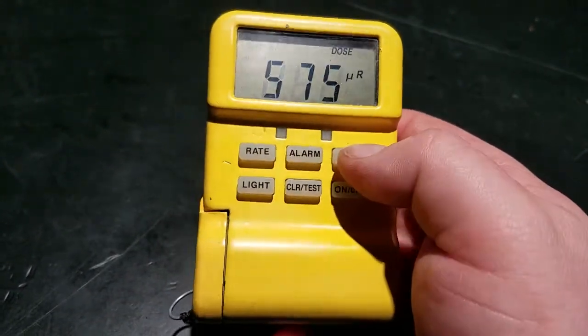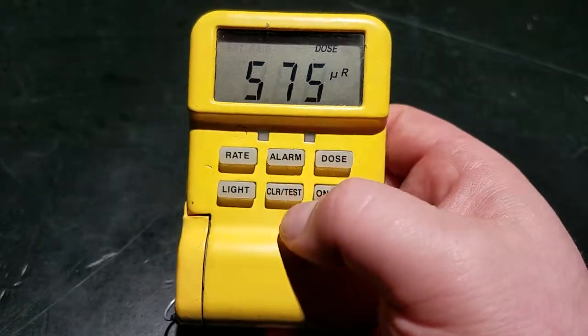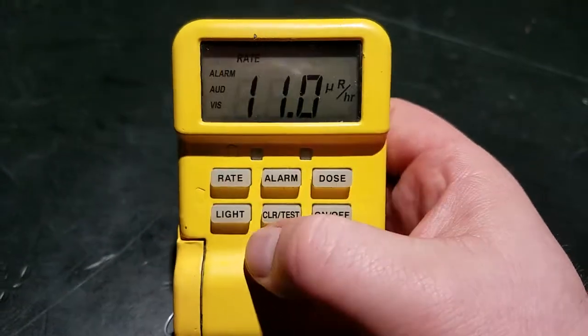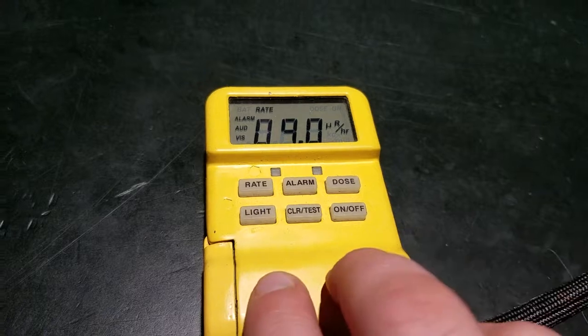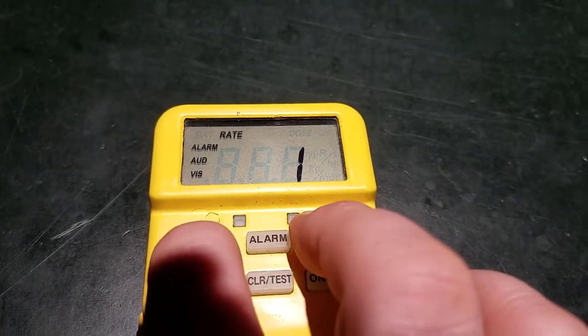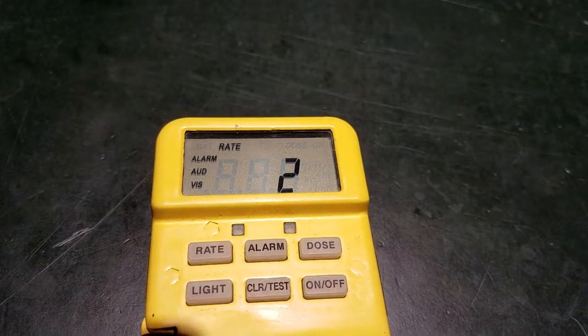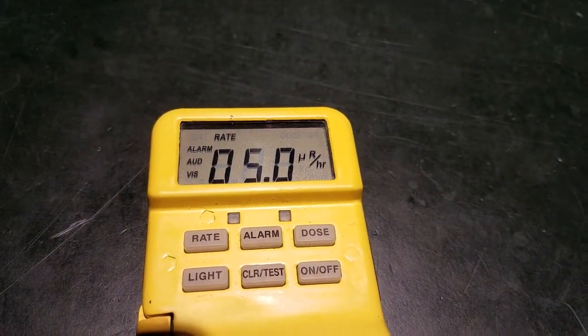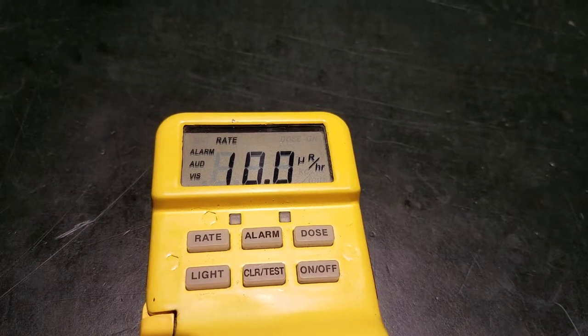The same thing with the dose. It also has a logging function. If you hold down these two, it's stored sample one. The next sample up is sample two. So it actually stored the current dose rate and the dose amount.